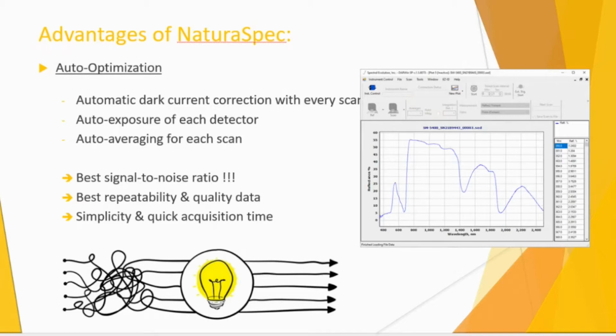And because each detector is treated independently from an exposure standpoint, you make sure that, if you're looking at, for instance, a very light sample, you will have very high signal-to-noise ratio in the UV-Vis region, because you have a very light sample, so let's say a lot of reflectance. But in the NIR region, you may be too dark. Well, our software will automatically adjust that.